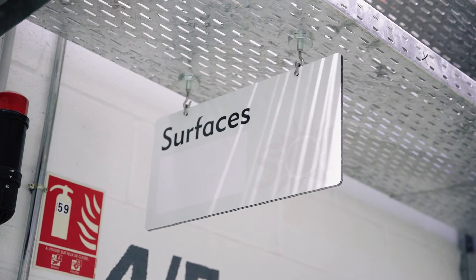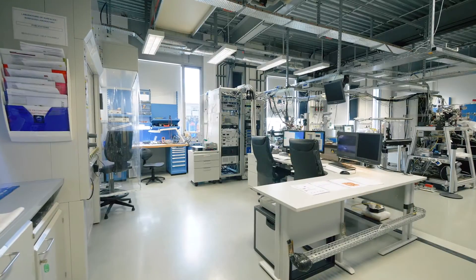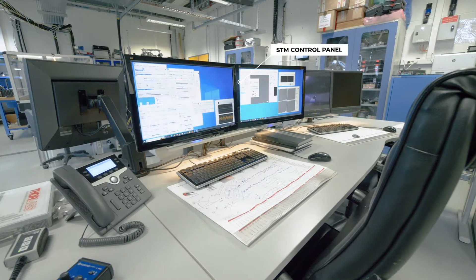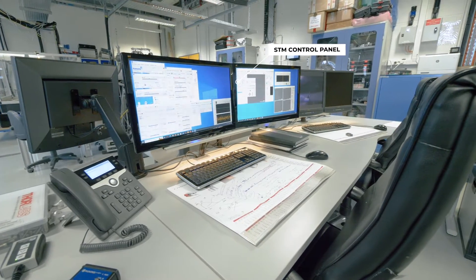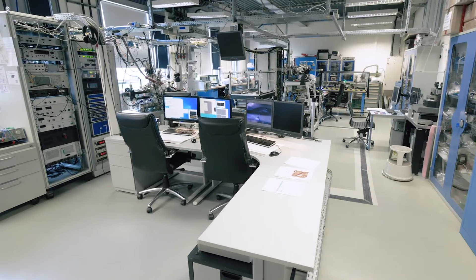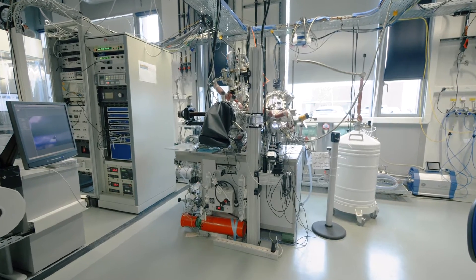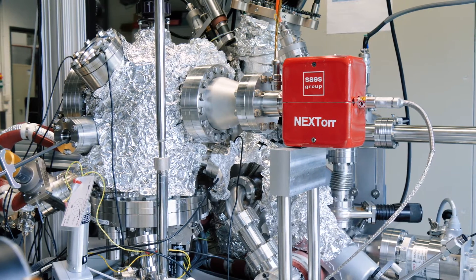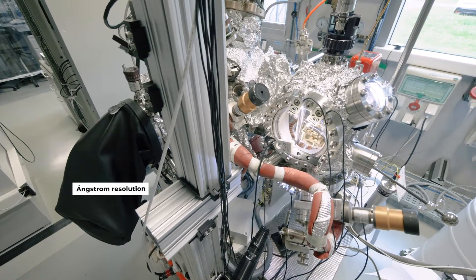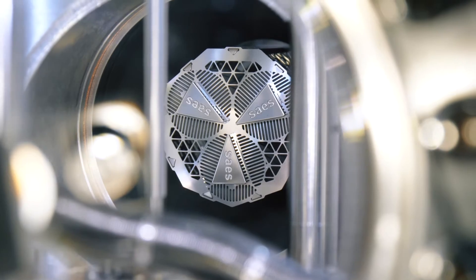Access is realized via the SOLEIL badge system. Entering the materials laboratory surface part, you immediately see the control panel of the scanning tunneling microscope, or STM. Scanning tunneling microscopy is the central complementary technique to several synchrotron-based techniques, since it allows for real space observation with angstrom resolution. The instrument is working under ultra-high vacuum conditions and can also perform in atomic force mode.